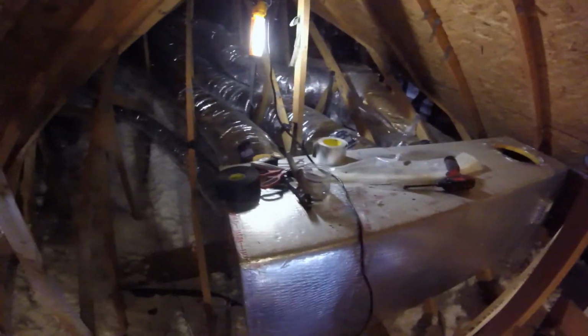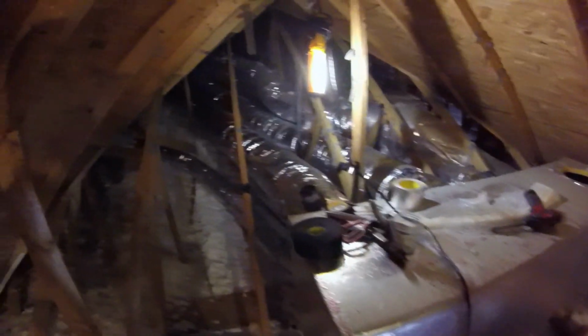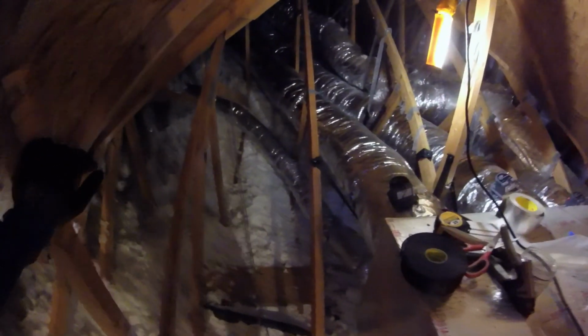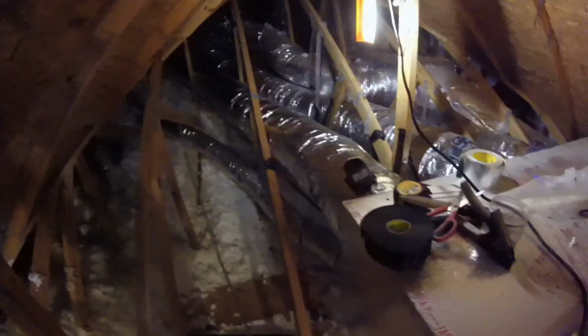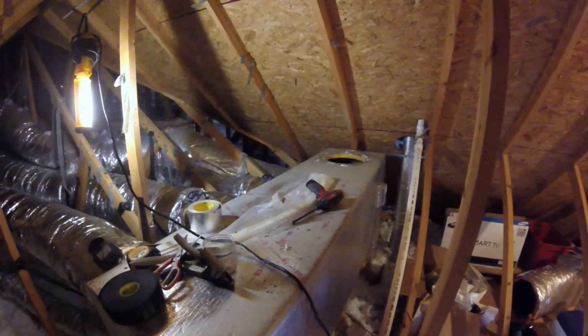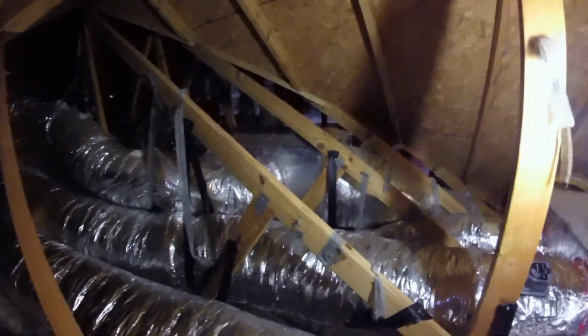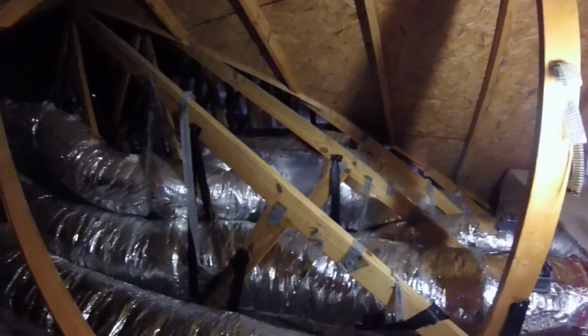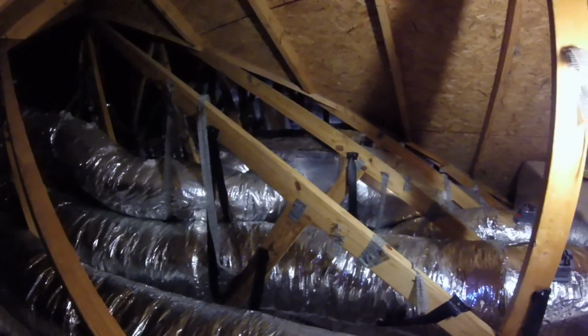Alright, I just finished getting all the dampers changed. Rerouting the ductwork. I got that thing open right now - that's where the bypass was, but it's gone now. I capped that return box where the bypass was feeding.